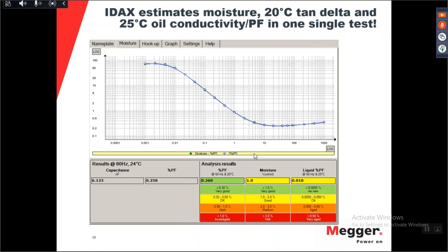And again, if we look at a generator step-up transformer, which takes very high currents and the temperature is very high, I would say that those 2% is probably very relevant. But if we look at a smaller distribution type transformer, it's very bad to say a smaller distribution type. I should maybe say a smaller transmission type or a larger distribution type transformer, 20 MVA or something like that. If you go above 3%, it is not critical, but then it starts to be critical.